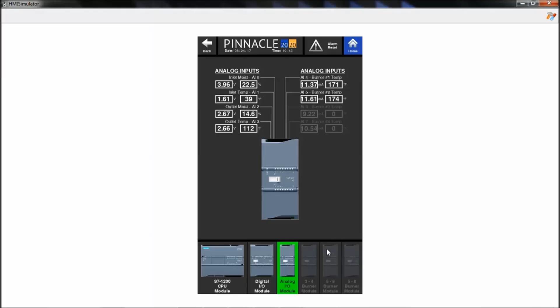These modules are also installed in this same orientation in the low voltage cabinet. At the very top left of the cabinet, you'll see these exact 3 components installed in this order and orientation. On the top left module, these are all the wires and inputs coming to that component, wiring into the top side. So if you find yourself trying to chase wires and see where they might be installed, you can use these menus to see exactly which wires are coming in, which module they plug into, and where exactly they connect.